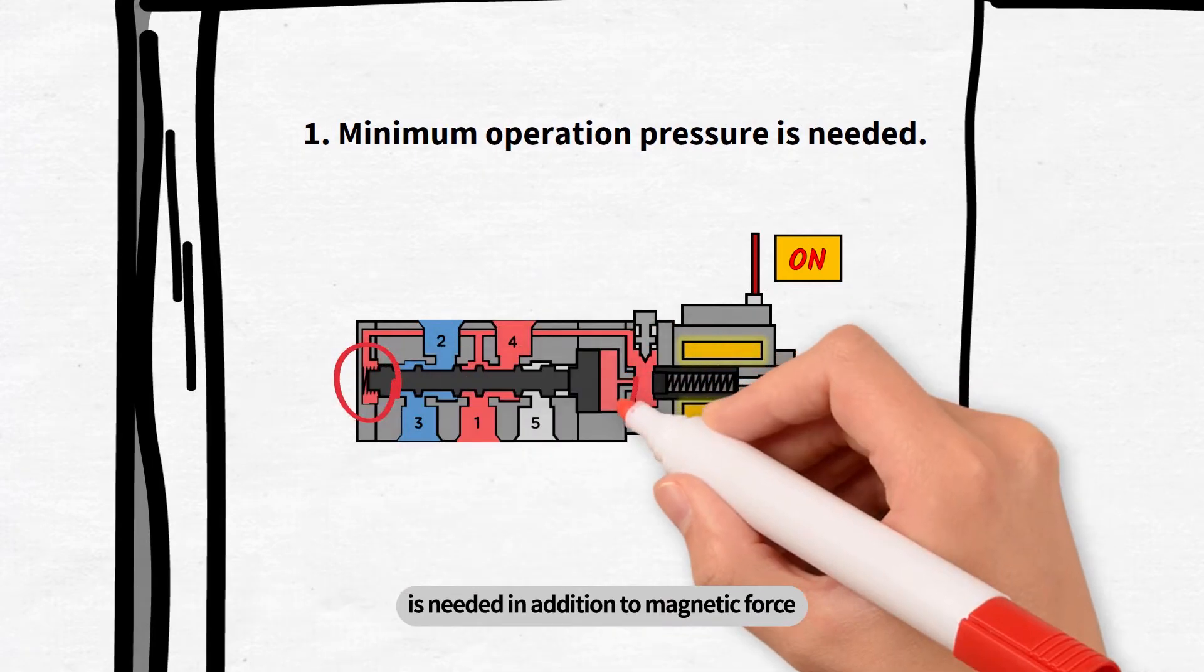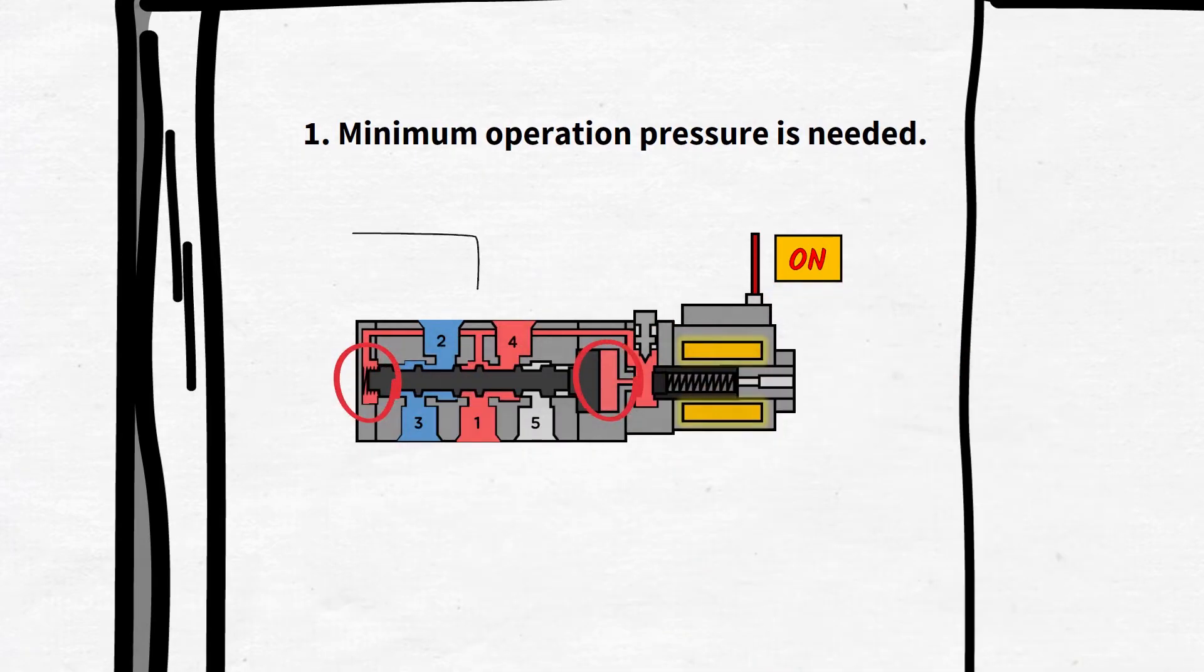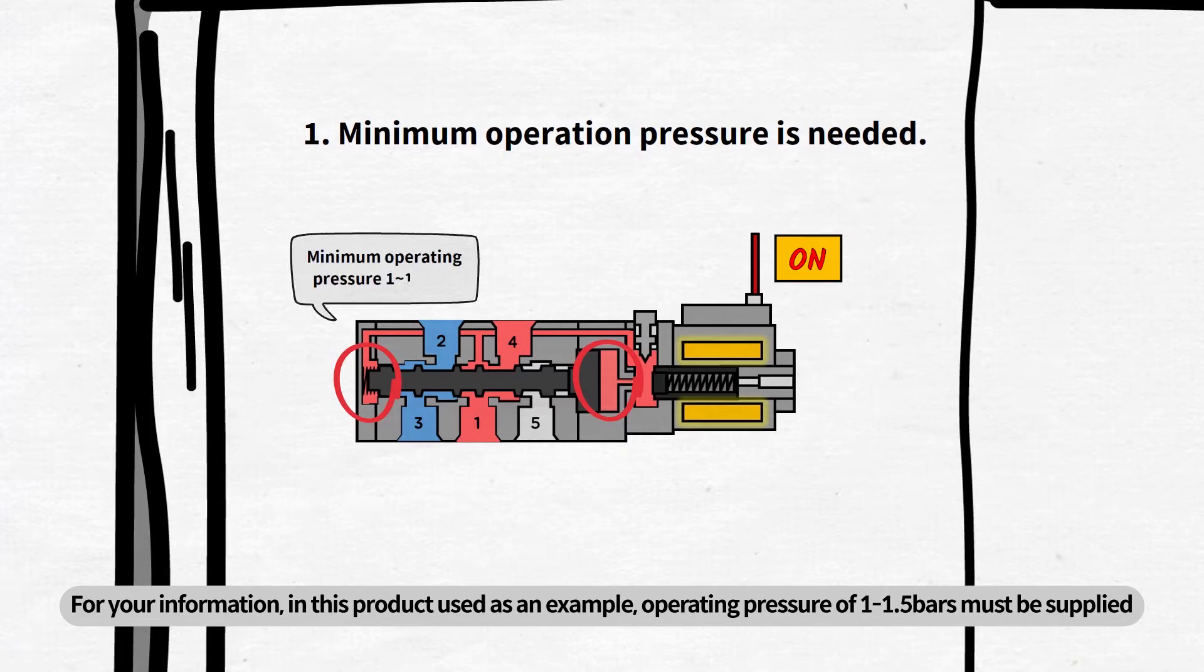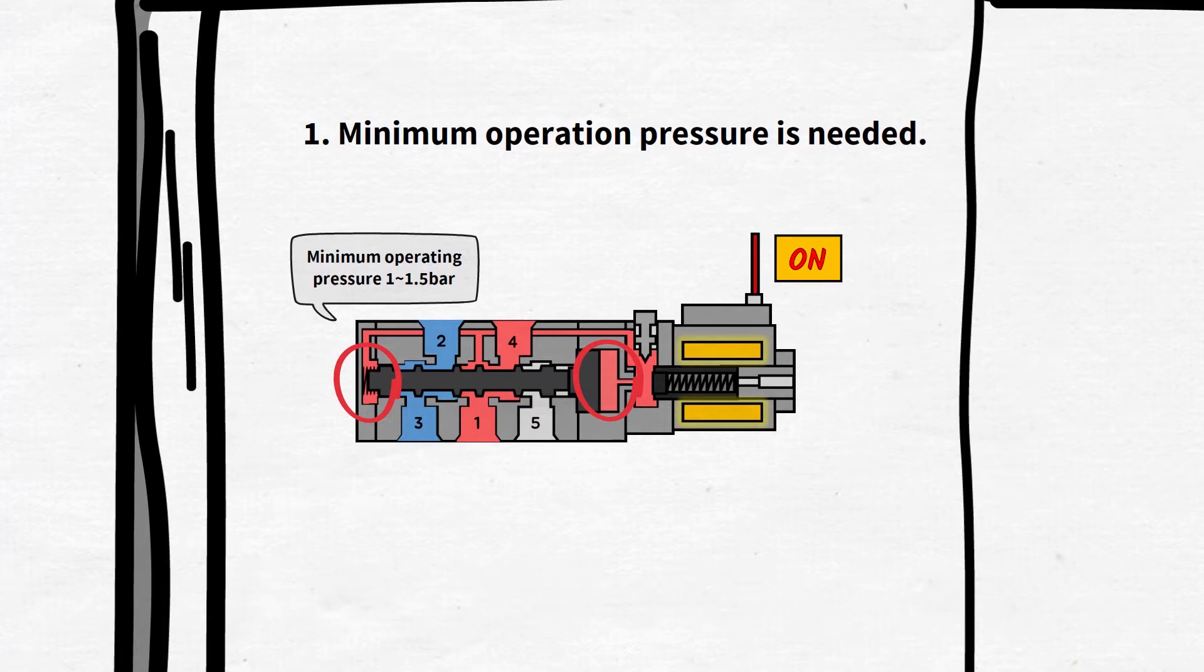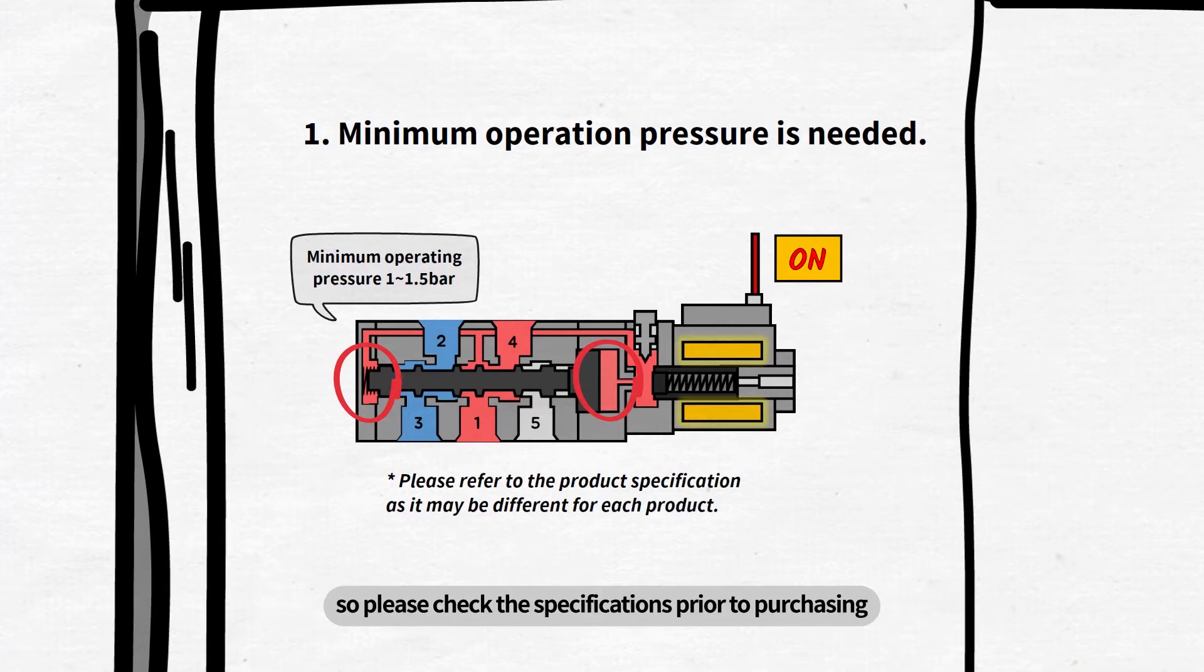compressed air with minimum operation pressure is needed in addition to magnetic force. For your information, in this product used as an example, operating pressure of 1 to 1.5 bars must be supplied. The minimum operation pressure for each product may be different, so please check the specifications prior to purchasing.